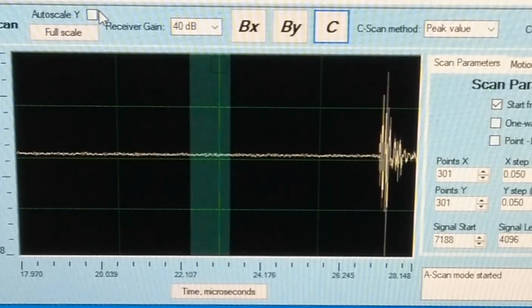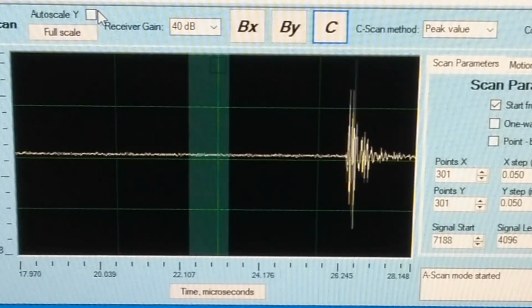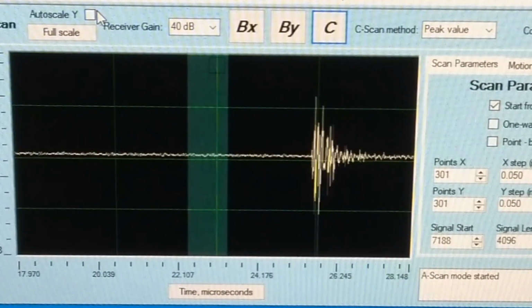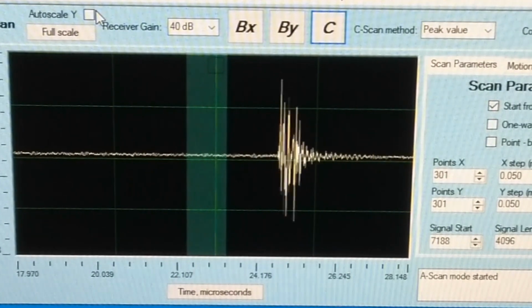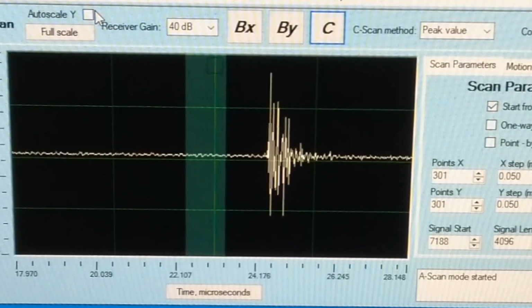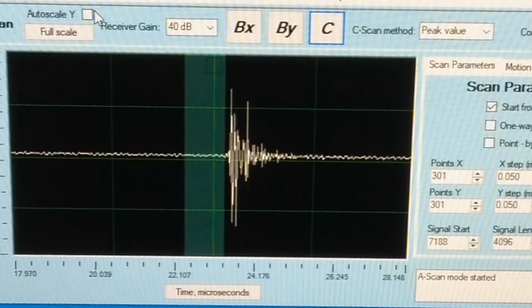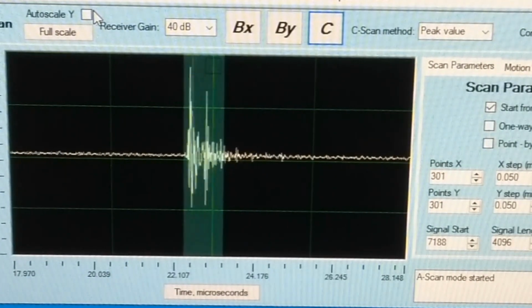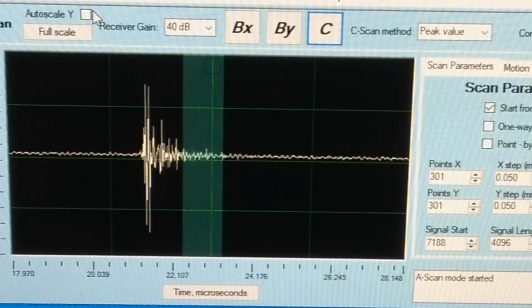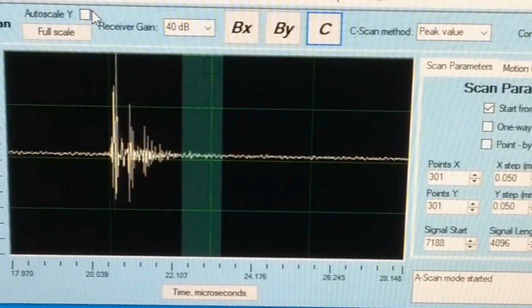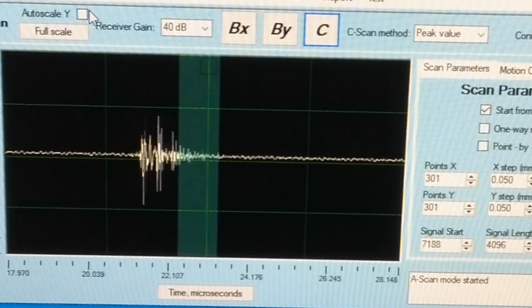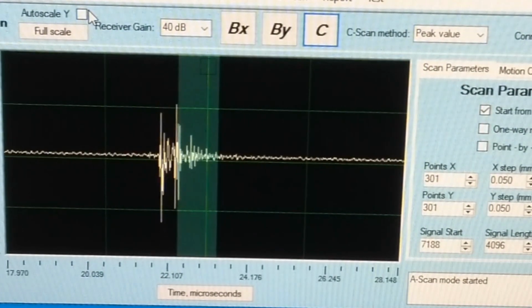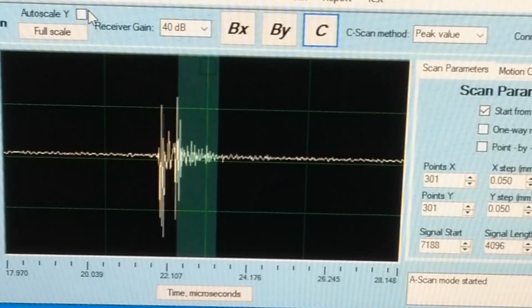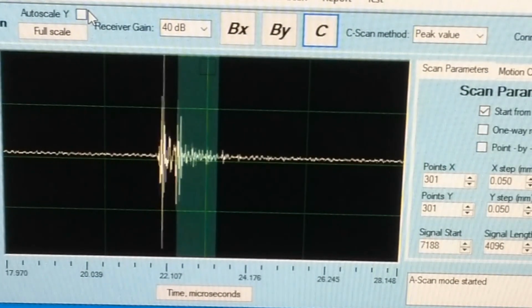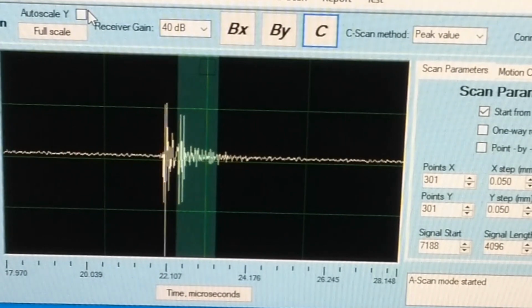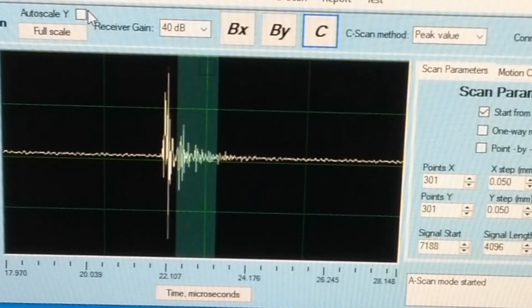By moving the transducer vertically toward or away from the sample, we are able to see a second pulse. The first pulse is a reflection from the top surface of the first plate, while the second pulse is a reflection from the bottom of the first plate. Since we are looking to focus on the gap between the two plates, we need to adjust the vertical position of the transducer until the amplitude of the second pulse reaches a maximum. The vertical green bar is known as the gates and will be used for creating the C-scan image.